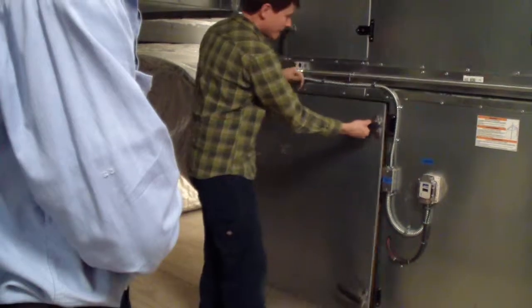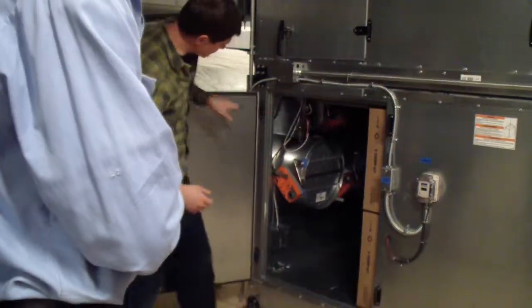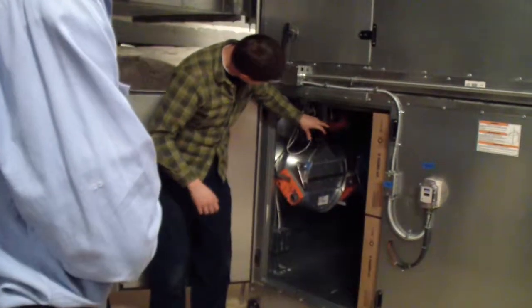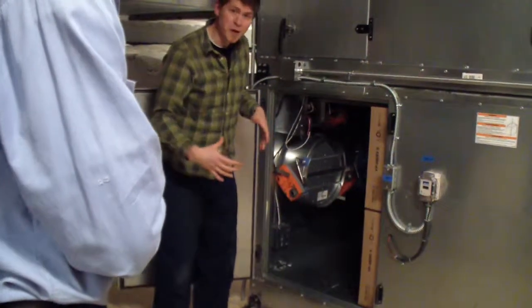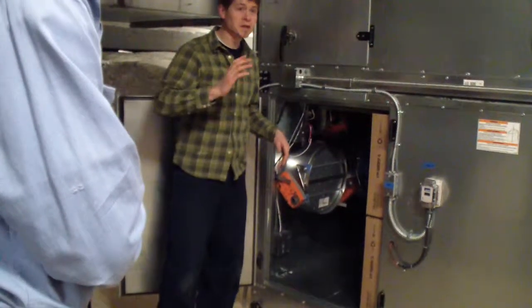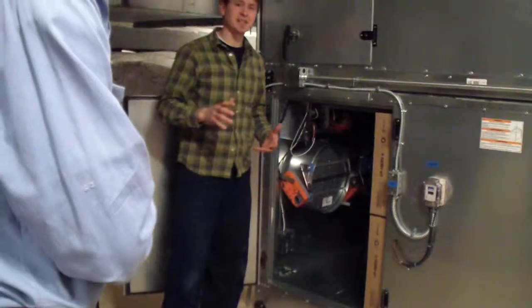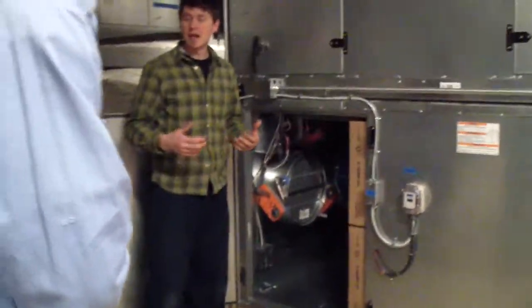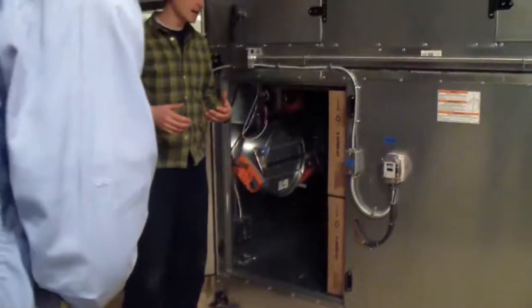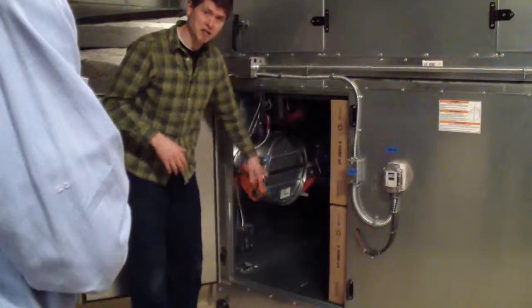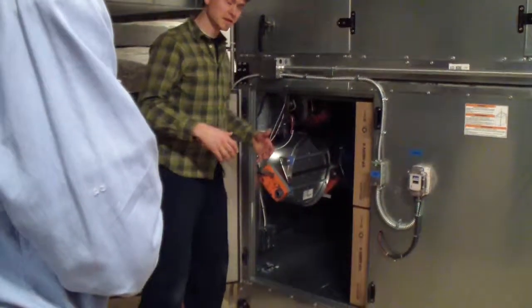As we had said earlier, you've got a 3 damper compartment. So your center one, which is an open-closed damper, is set for your 2,500 minimum CFM outside air coming in. And then the other 2 are modulating for your economizer position.